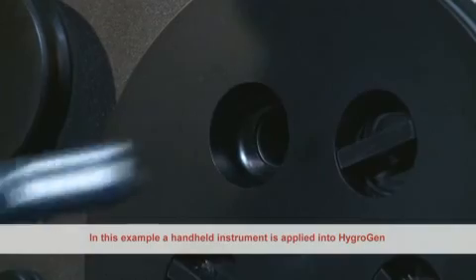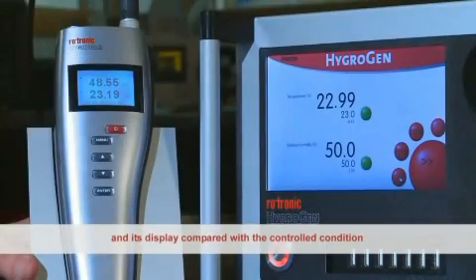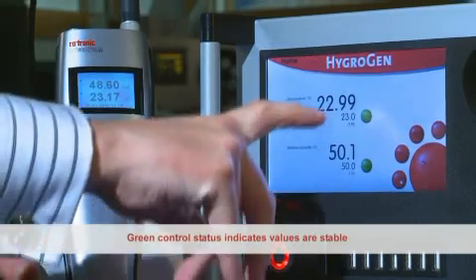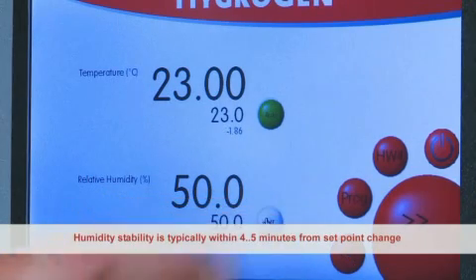In this example, a handheld instrument is applied into the HygroGen and its display compared with the controlled condition. Green control status indicates values are stable, at which point the user can check instrument calibration. Humidity stability is typically achieved within four to five minutes from a set point change.